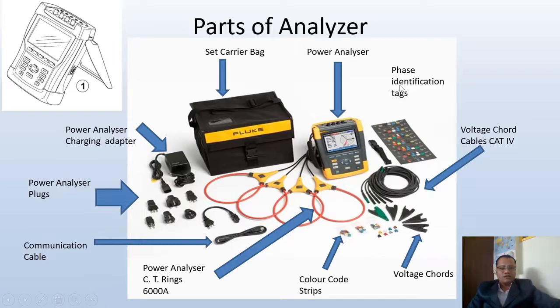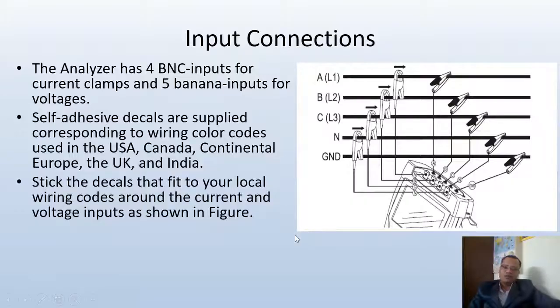These rings are the current transformer rings which come along with the power quality analyzer. Another part is the color-code strips — you can use these rings for notation purposes and attach them here since all the rings look the same. Then voltage cords — five cords are provided for voltage, and four CTs are provided: three for the three phases and one for the neutral. You have to measure voltage with respect to ground, so neutral, ground and other three phases are included.